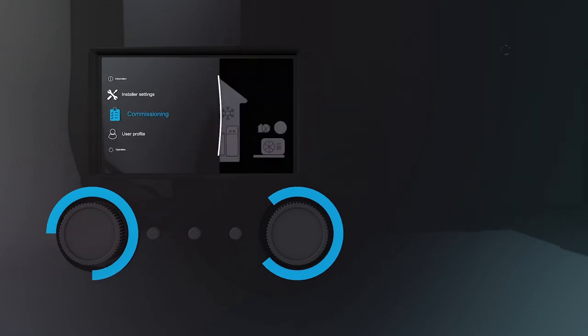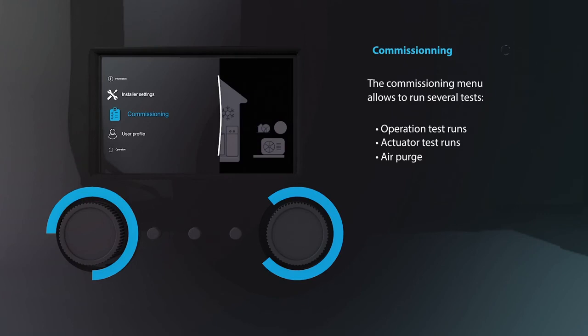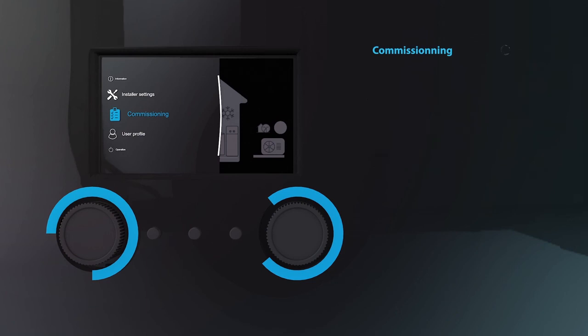Scroll down to the commissioning tab and you'll find several tests that can be done to check if the installation runs smoothly. These include operation test runs, actuator test runs, an air purge, and if applicable, an underfloor heating screed dryer test.